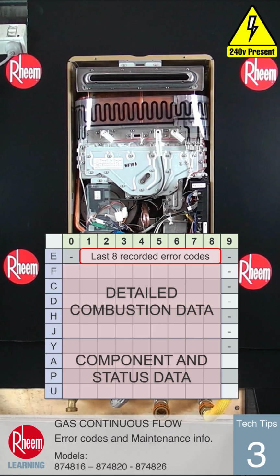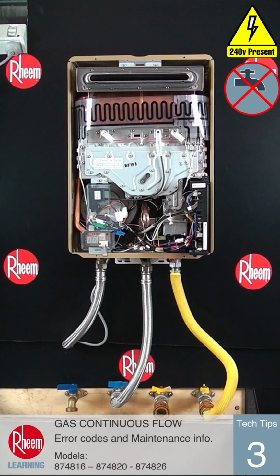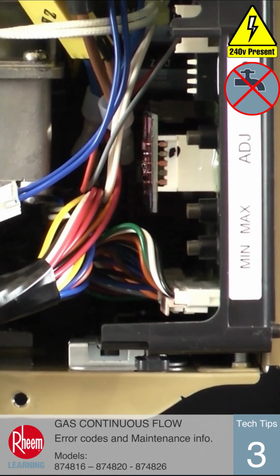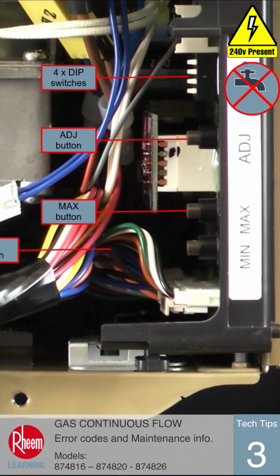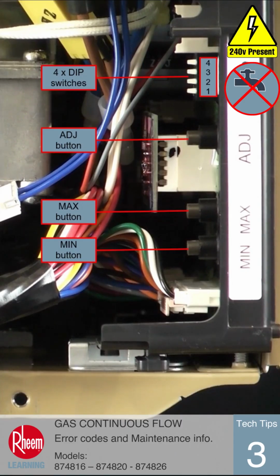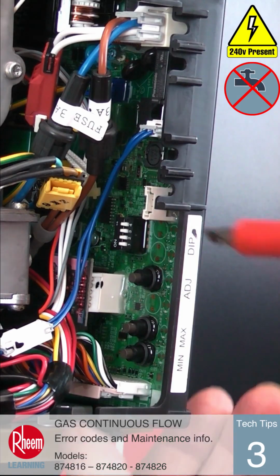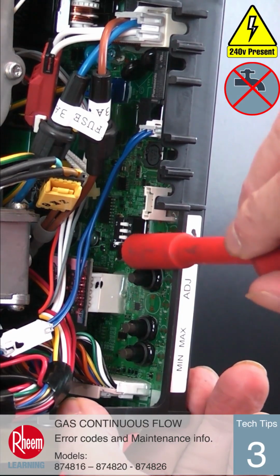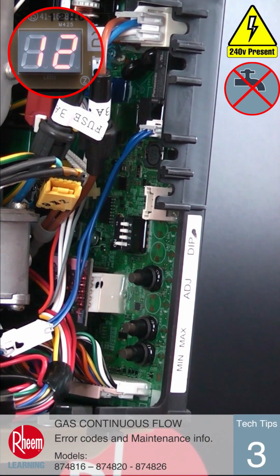The table also has combustion operation data, and the rest of the table gives access to live data from the internal components. To access the data direct from the unit, remove the front cover and locate the dip switches and the max and min buttons on the PCB. Turn on dip switch number 1 by pushing it towards the rear of the unit using an insulated tool. The front LED display will show 1E followed by a number.